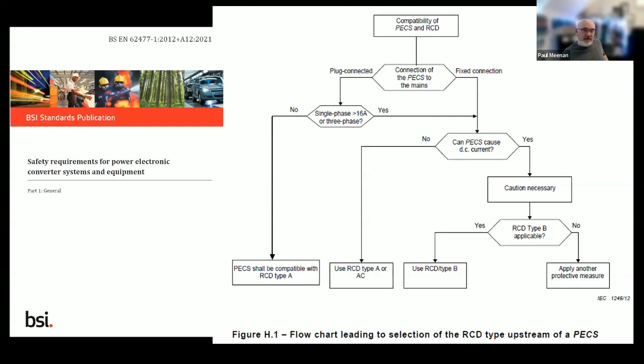But yet in our wiring regulations, we still have type AC, although it's strongly recommended that they're not used, and they have been banned around various parts of Europe. So it's really important that you look at what your fixed installation will do. Is it a communications rack? Will it produce DC leakage from the switch mode power supplies? Of course it will. And if it does, is type A enough? Have we done enough?